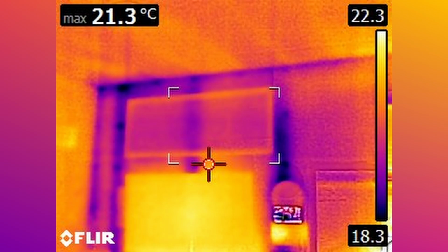Thermal bridging is also a concern for typical North American houses. This is the phenomenon where heat will transfer through the studs in the exterior walls of a home. If you look at this image, you can clearly see the studs in the wall. Now, keep in mind, this was not an extreme temperature day. The outside temperature was only -10, and the interior temperature was typical room temperature, about 20 degrees. Yet, you can clearly see the studs, almost like I pulled the drywall off the walls.